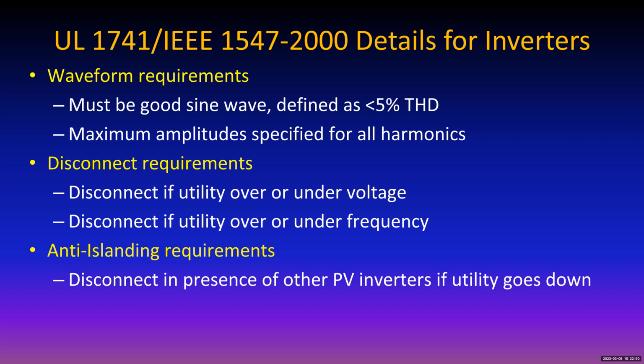And probably one of the most important, these are all important features as far as the utility is concerned, the anti-islanding requirements. And this is where that current source part comes in handy, because the current source is synchronized by the utility voltage. If the utility voltage goes away, the current source loses its synchronization and it starts drifting, its frequency changes to the point where it goes out of range and the microinverter has to shut down, or the big inverter if it's a big one.